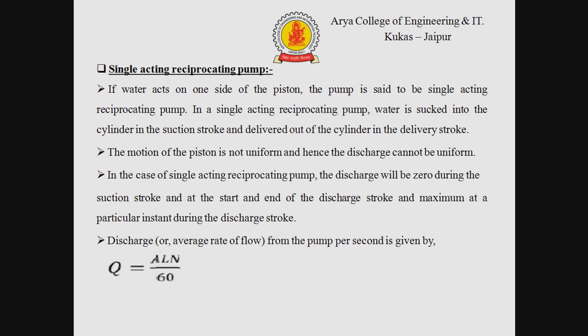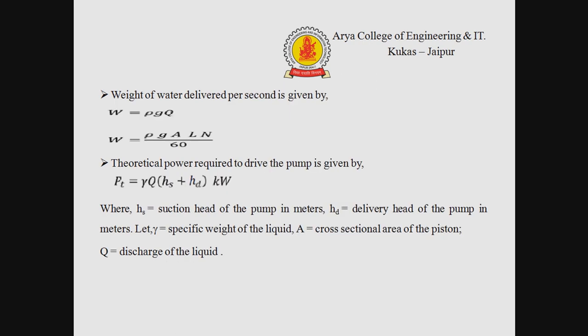Now we discuss the single acting reciprocating pump. If water acts on one side of the piston, the pump is said to be a single acting reciprocating pump. Water is sucked into the cylinder during the suction stroke and delivered out of the cylinder during the delivery stroke. The motion of the piston is not uniform and hence the discharge cannot be uniform. The discharge will be zero during the suction stroke and at the start and end of the delivery stroke, and maximum at a particular instant during the delivery stroke. The discharge from the pump per second is given by Q = ALN / 60, where A is the cross-sectional area, L is the length, and N is the RPM.